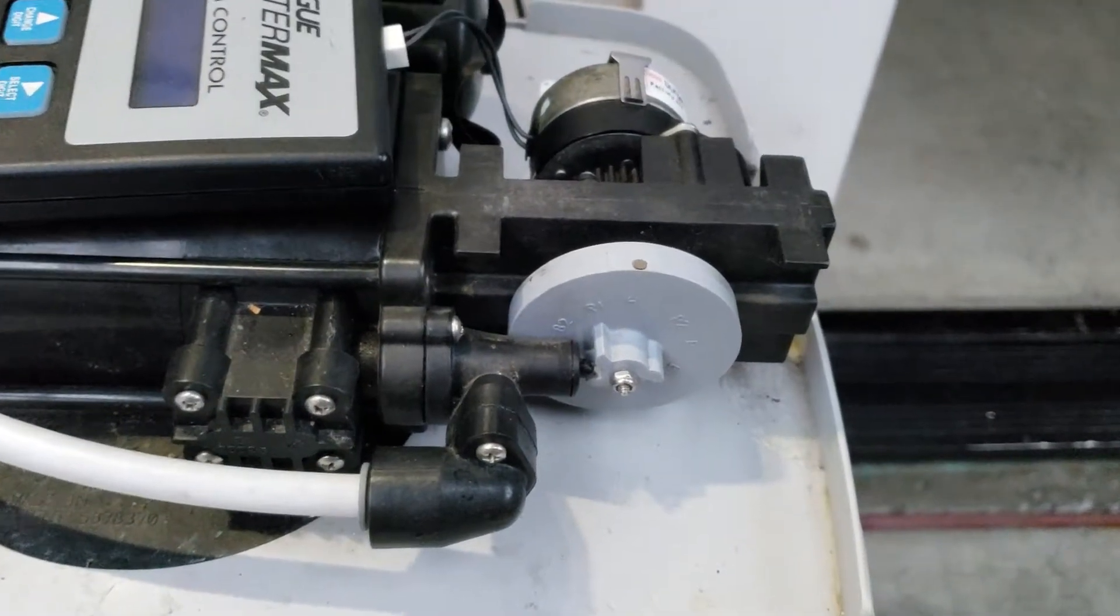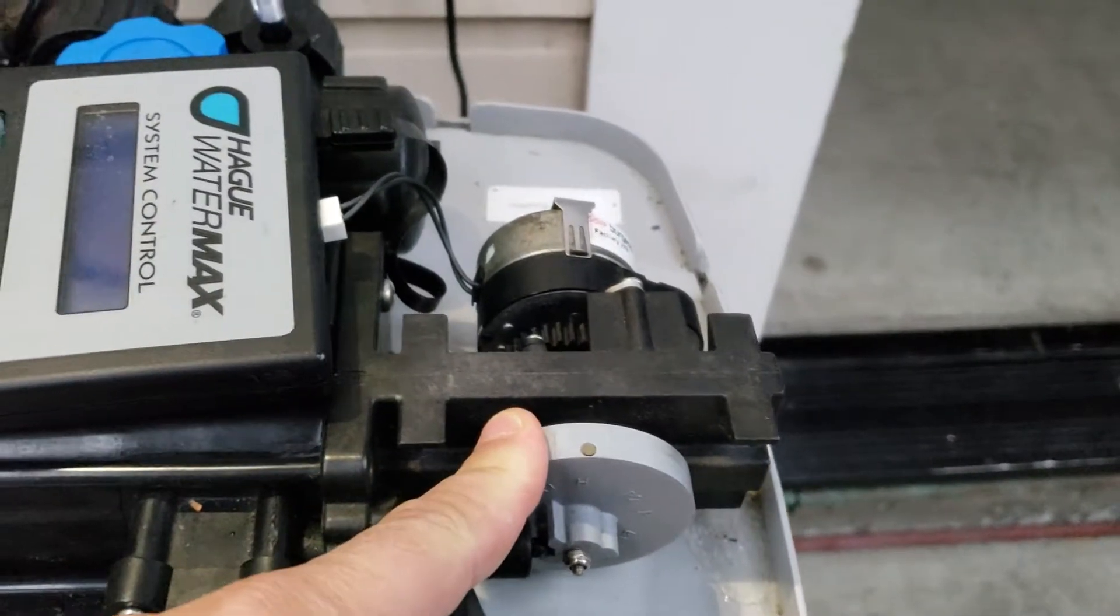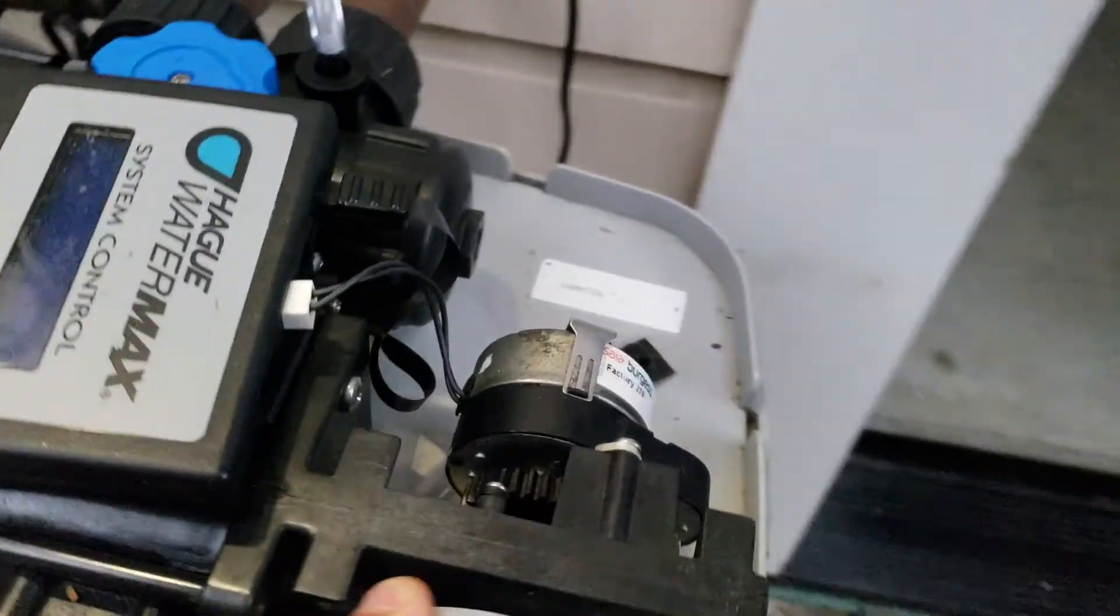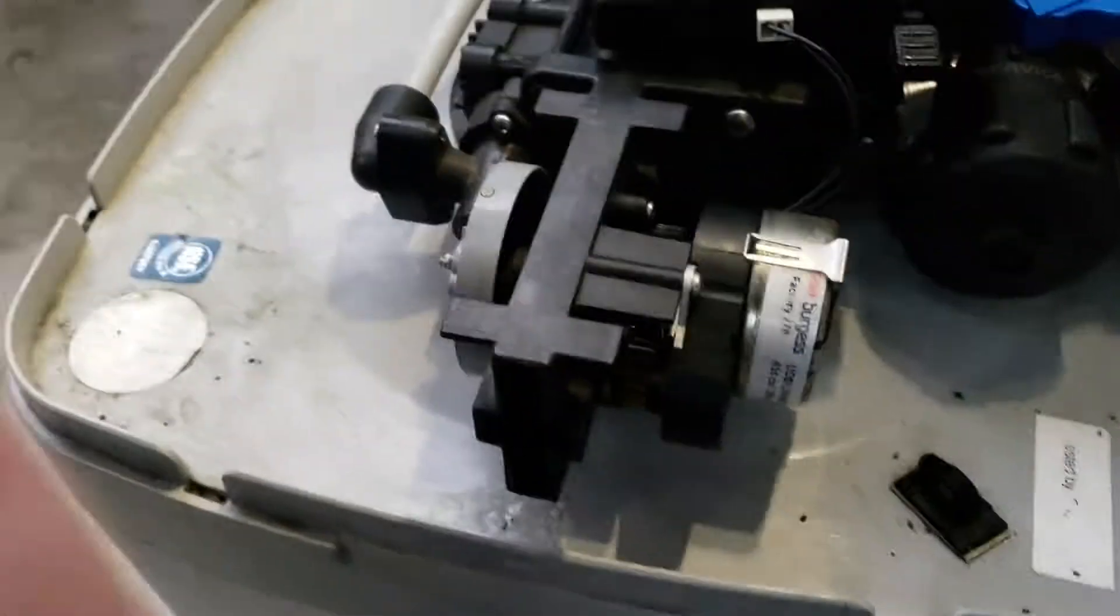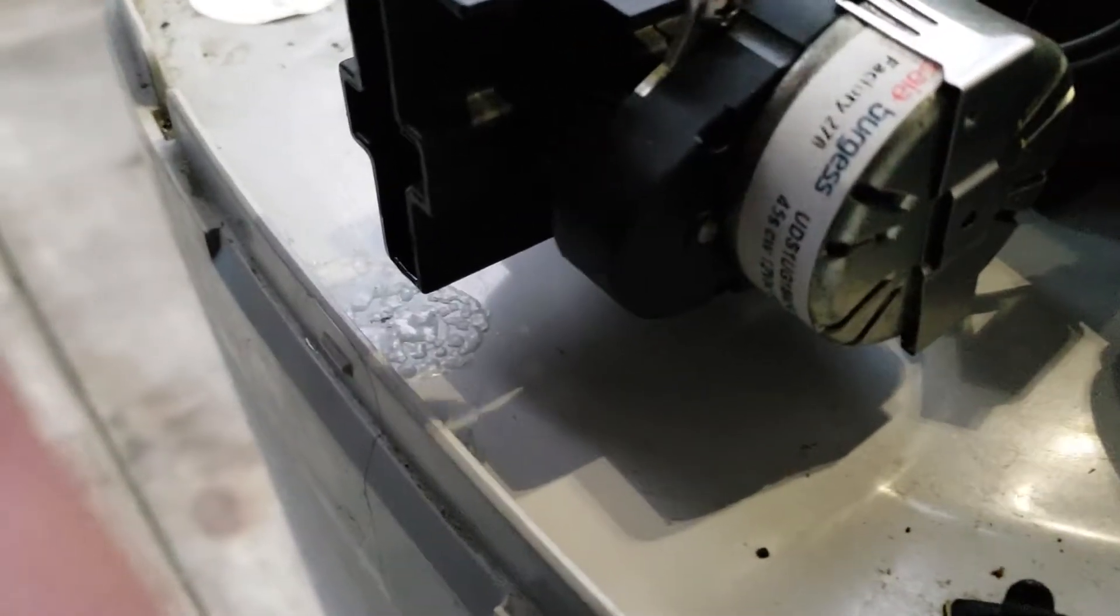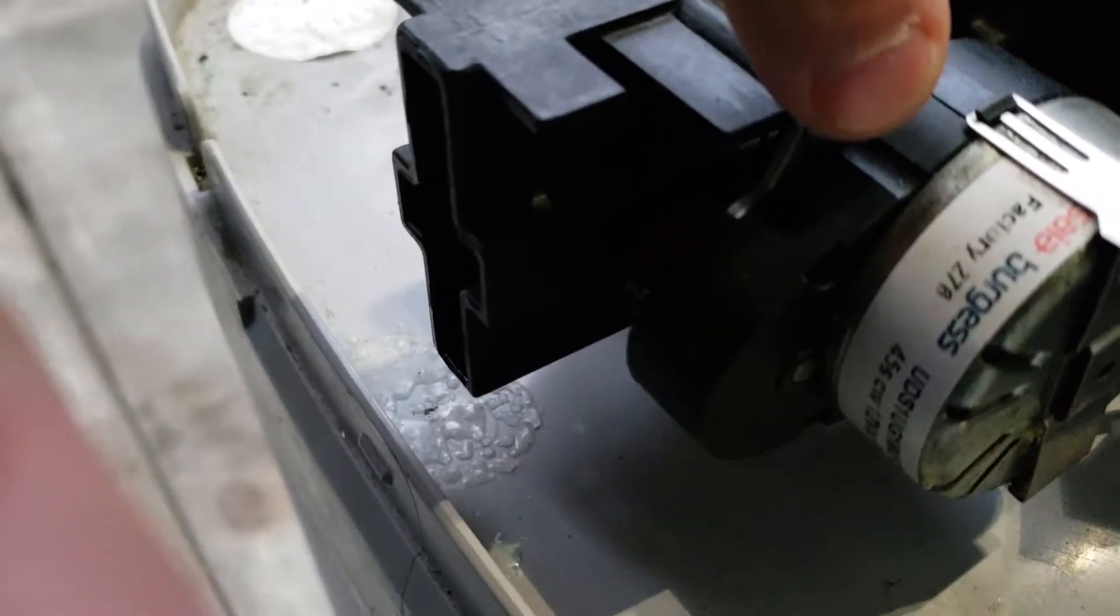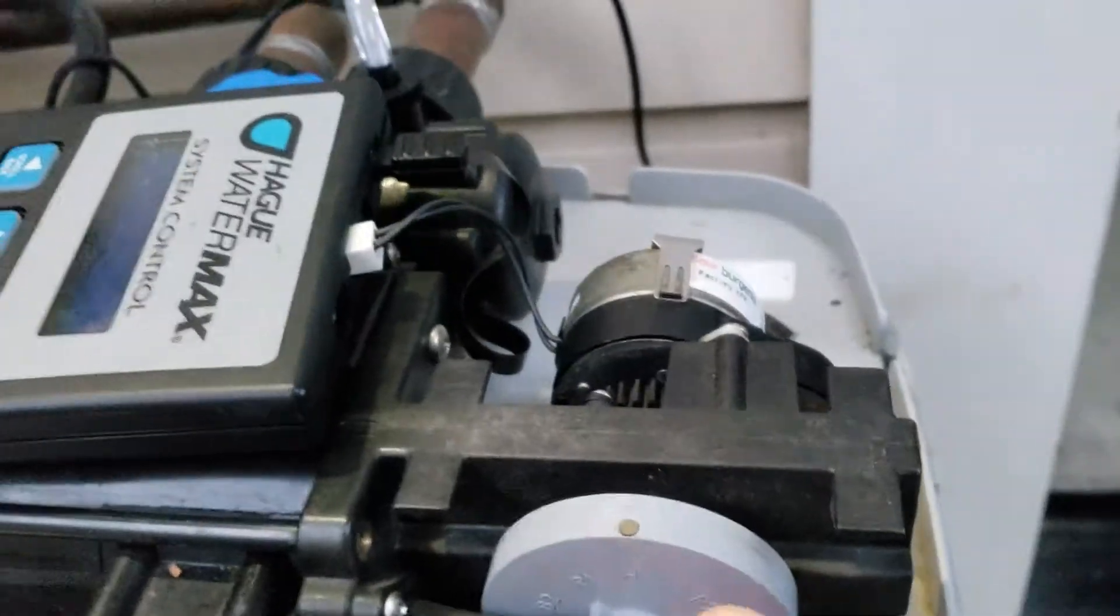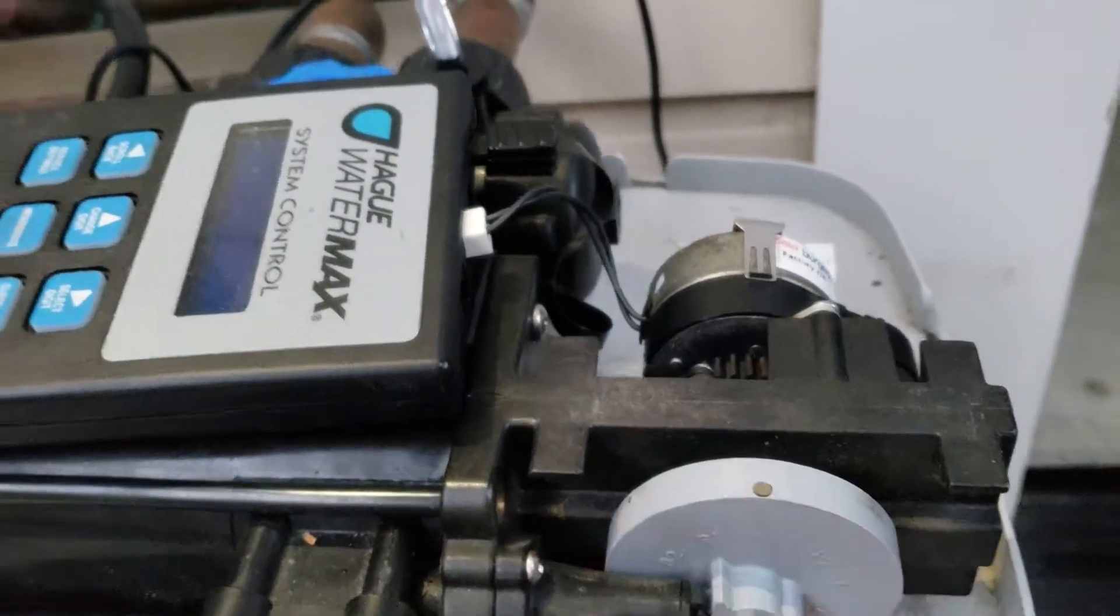If for some reason this wasn't functioning, then the next thing you could do would be to take this top screw off of here, twist this motor down, and then manually turn this to its top dead center position.